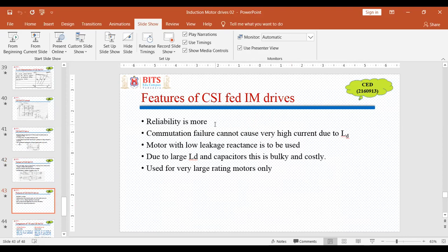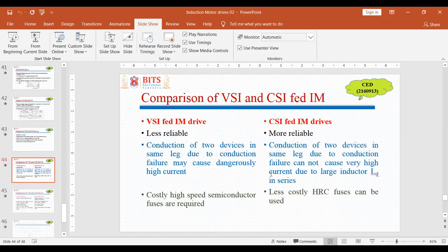These are the features which we have already discussed in yesterday's class. It is more reliable and commutation failure cannot cause very high current because there is a large inductor present in series. A motor with low leakage reactance is to be used here. Due to the large Ld and capacitors, this is a bulky and costly system, used for very large rating motors only. This is the comparison of VSI and CSI-fed induction motor drives.